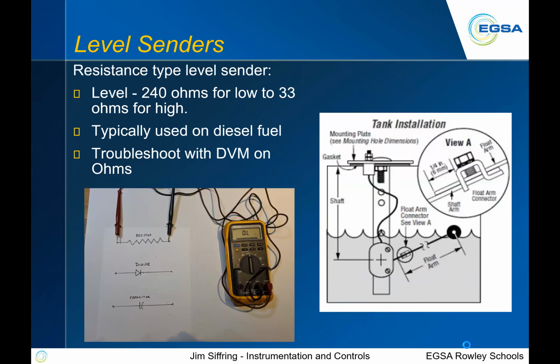Probably one of the more common ones you'll see, in the right-hand graphic, is just a variable resistor that's on a float arm. That arm is connected to a variable potentiometer or resistor, and as fluid goes up in the tank, the arm is taken across that variable resistor and changes resistance out. So again, we're using that 240 to 33 ohms scale. That's common. It's not a rule, but it's very common. Use these a lot on diesel fuel tanks. You won't see these in gasoline tanks at all, but you will see them in diesel tanks.